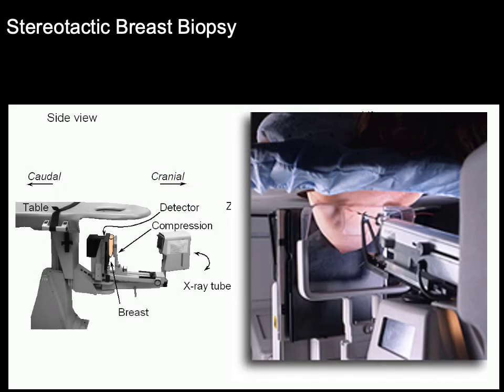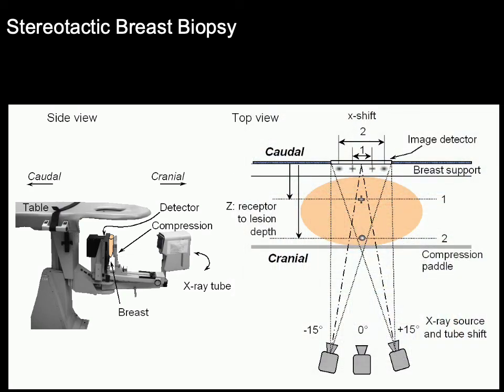Another mammography application is stereotactic breast biopsy. The patient's breast is placed under compression. A typical mammogram obtains an image with the x-ray tube in line with the detector, but in stereotactic breast biopsy, two images are required to create a stereo pair — one at plus 15 degrees and another at minus 15 degrees. By lining up the object in both images, we can use geometry to determine the depth of the lesion within the breast, which is used to guide the needle during biopsy.